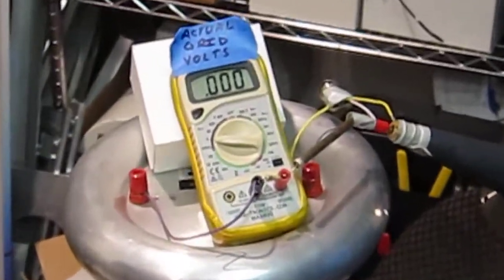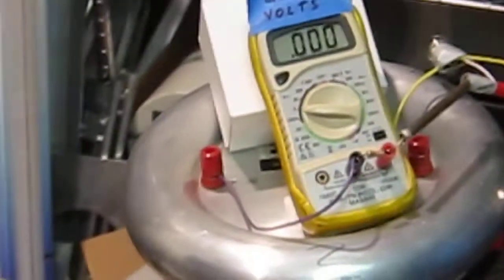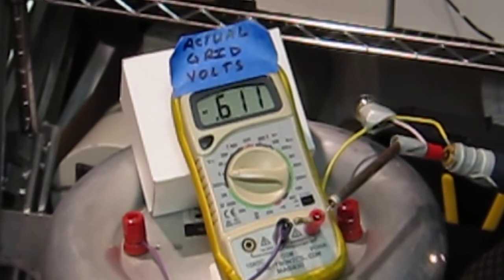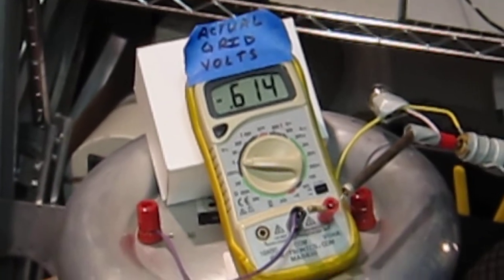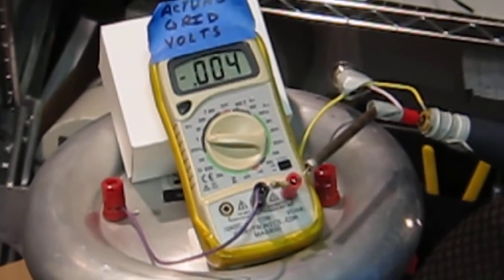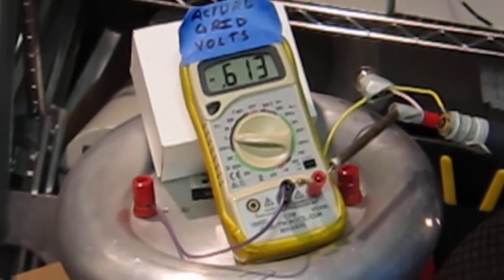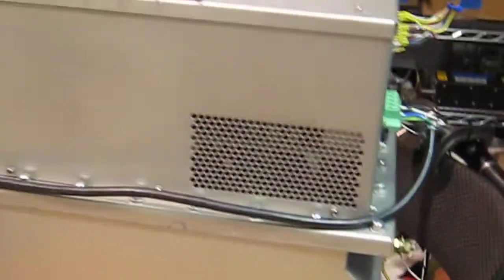And now I will enable the grid voltage by flipping this toggle switch right here, and you can read it on that meter. I'm not going to get very close to the thing right now. And there I have minus 614 volts DC, and I can turn that off and on. I won't be able to adjust it right now because there is no X-ray tube to enable the normal servo loop function. And here I'll be able to read the high voltage from the Glassman voltage divider that I've added. It's also a dummy load resistor for the thing to simulate tube current through the X-ray tube.